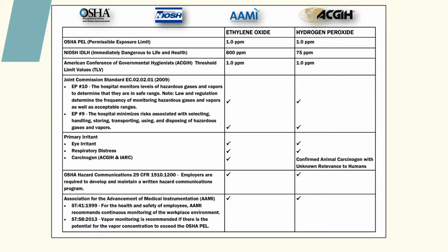So again, these blank spaces are there because we feel like there needs to be more research done. There needs to be more studies, and we need to figure out how harmful it really is. And just to make a note, in certain places, and I'll talk about this going forward a little bit too, in certain states, Hawaii and Washington, they do have a 15-minute time-weighted average, and that's 3 ppm. Other countries, the UK, certain parts of Canada, actually use a 15-minute STEL, and that's 2 ppm.